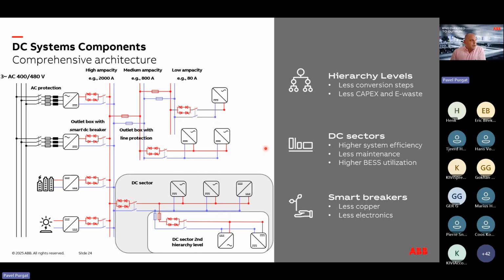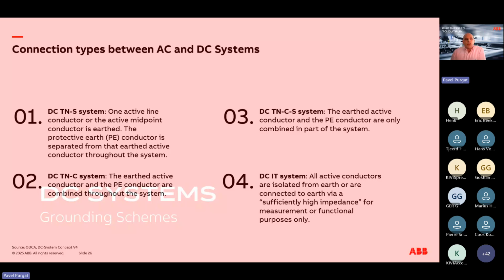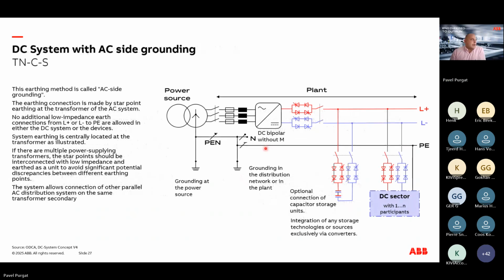What is influencing the choice of the protection in DC are the grounding schemes. Now, in principle, the grounding schemes in DC are very similar to AC, but it still makes for an interesting discussion to have a look at these options. The first option is the grounded system on the AC side. So in principle, we can have a transformer that will be Y connected, and the ground will be connected on the AC side and then used across the DC system.